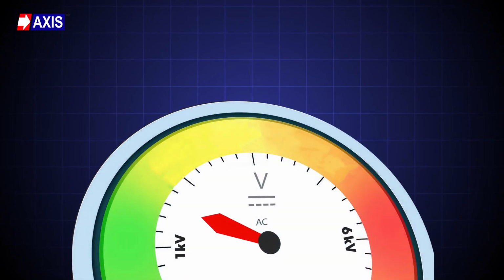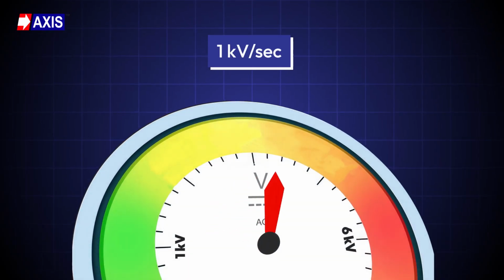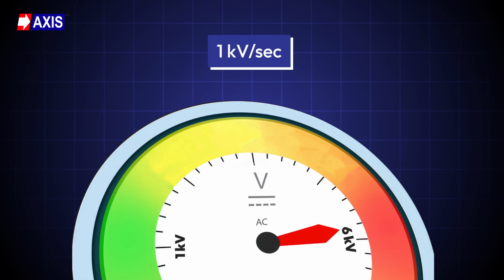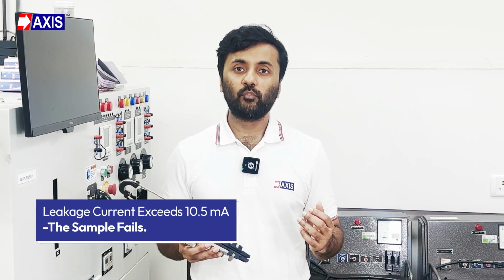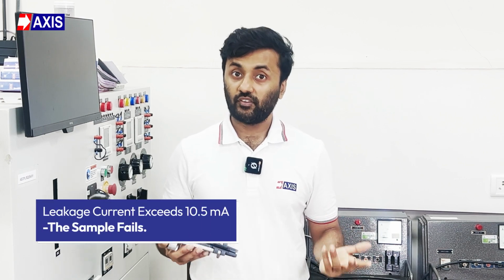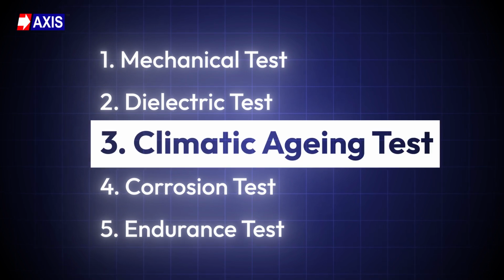Gradually increase the AC voltage at a rate of 1 kV per second until it reaches 6 kV. Maintain this voltage for 60 seconds. If flashover or breakdown occurs or the leakage current exceeds 10.5 milliamps, the sample fails. Thirdly, the climatic aging test.